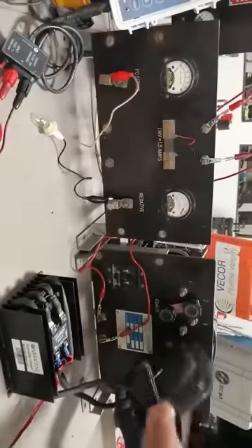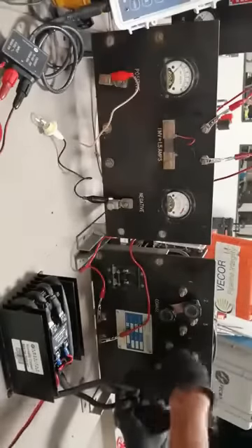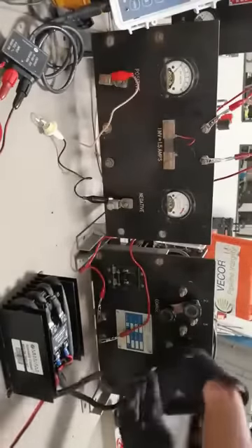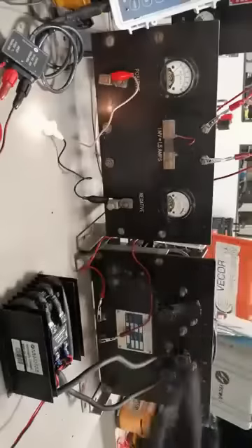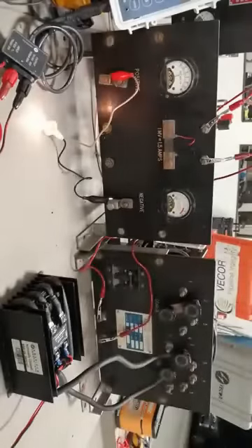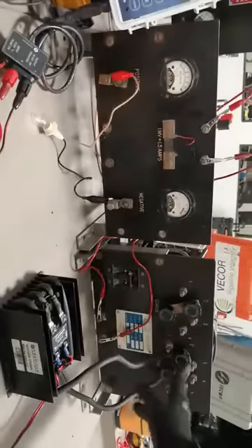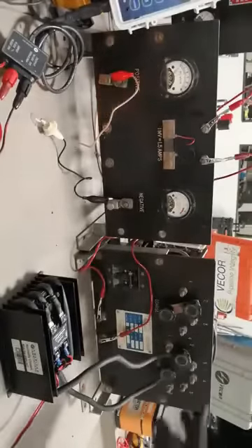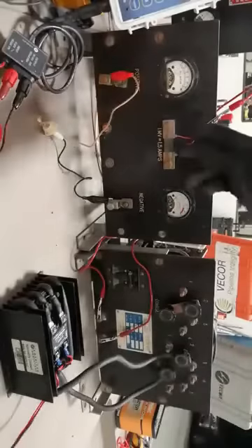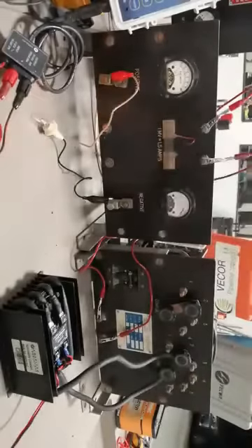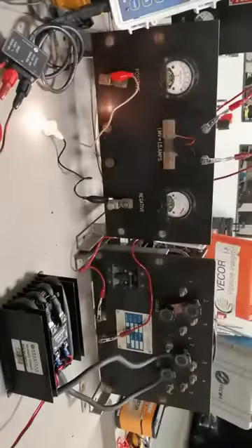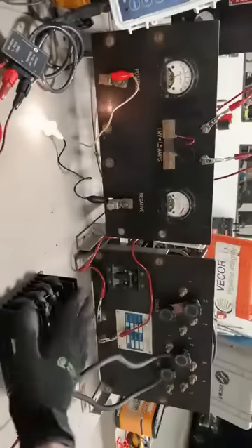Next, we proceed to activate the rectifier, and we thoroughly check and verify if it is causing any interruptions in the system. It is important to notice that it is also interrupting the AC power, which is the one that arrives at the AC-DC converter, and also the outlet. Notice that the voltage goes to 0, indicating that I'm dropping the voltage and achieving an interruption. This way, I would protect the equipment.